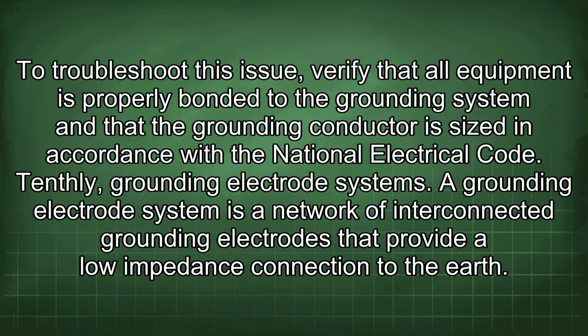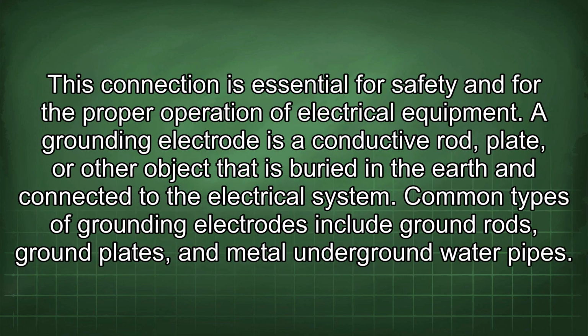10th, grounding electrode systems. A grounding electrode system is a network of interconnected grounding electrodes that provide a low impedance connection to the earth. This connection is essential for safety and for the proper operation of electrical equipment. A grounding electrode is a conductive rod, plate, or other object that is buried in the earth and connected to the electrical system. Common types of grounding electrodes include ground rods, ground plates, and metal underground water pipes.